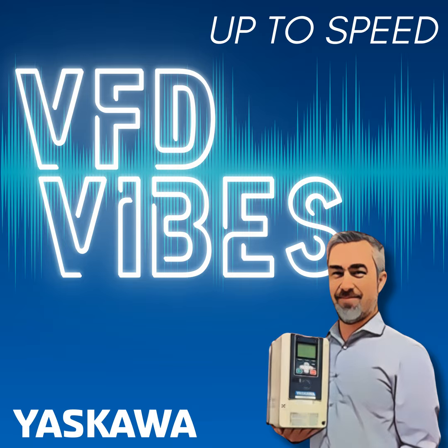Controls is sending me a run command. We've been working on this for an hour. We're certain it's a bad drive. Okay, hold on. Do you have a jump wire? Yep. Let's put that jump wire in on S1 and SN. So I'd be sitting there on the phone waiting, maybe a few seconds, a minute. He'd say, oh, my motor just started.